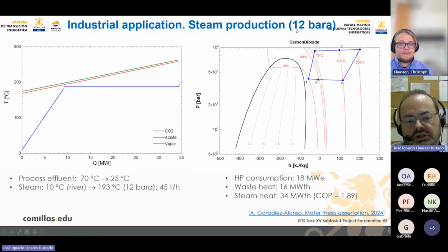Well, this is with 12 bar absolute. In this case, the source moves to 70 to 25 Celsius degrees, and we take water from a closed river, and we produce steam at this pressure, that is, with this temperature. Okay, this is the temperature heat release profile. In green, the CO2, in red, the thermal oil, and this is the steam produced. Okay, with some small superheating, as you can see here.